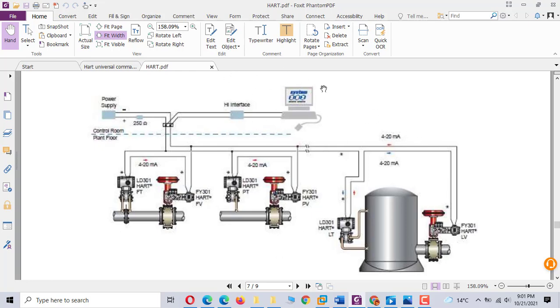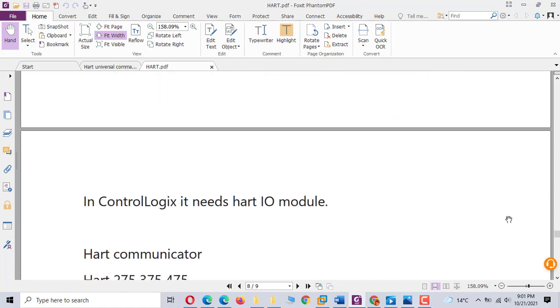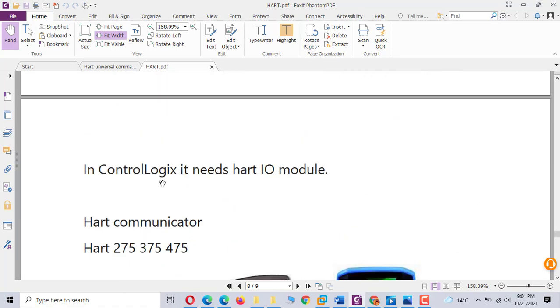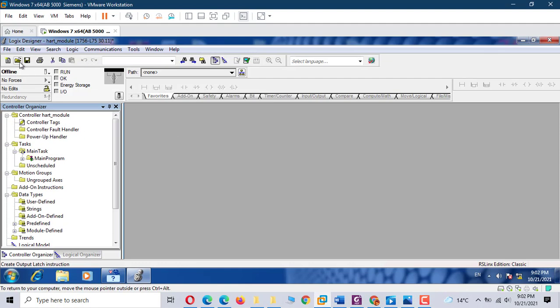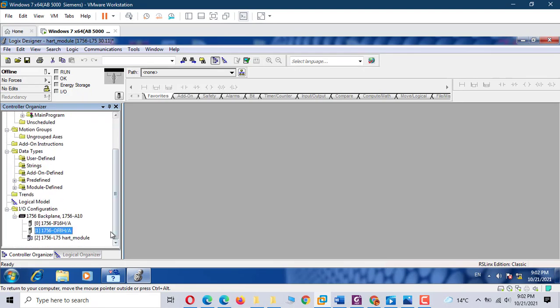Configuration is the parameter. In the ControlLogix PLC, you can't just use the analog I/O module. You have to use the HART I/O module. Let's look at this one. This one has the HART analog input module. This is the HART analog output module. So if you do something, you have to do configuration.